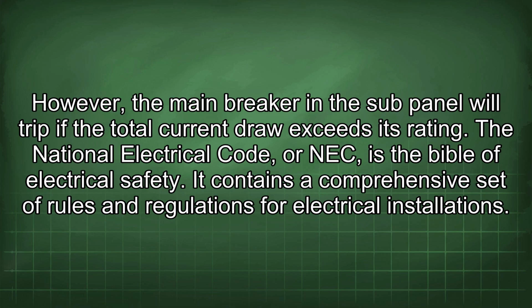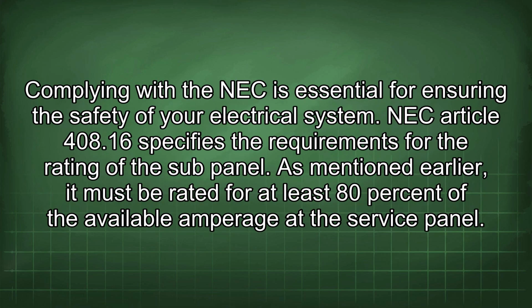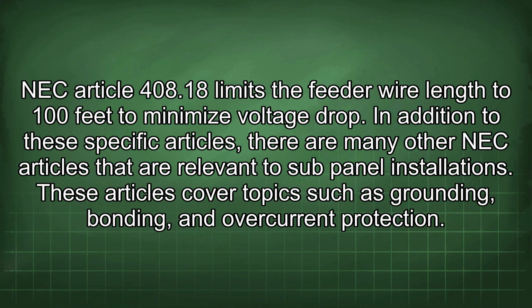It contains a comprehensive set of rules and regulations for electrical installations. Complying with the NEC is essential for ensuring the safety of your electrical system. NEC Article 408.16 specifies the requirements for the rating of the sub-panel. As mentioned earlier, it must be rated for at least 80% of the available amperage at the service panel. NEC Article 408.18 limits the feeder wire length to 100 feet to minimize voltage drop.